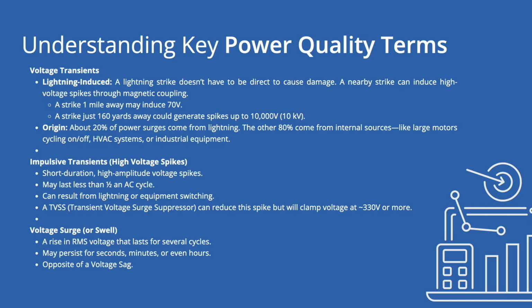Origin. About 20% of power surges come from lightning. The other 80% come from internal sources, like large motors cycling on and off, HVAC systems, or industrial equipment. Impulsive transients, high voltage spikes. Short duration, high amplitude voltage spikes may last less than half an AC cycle, and can result from lightning or equipment switching. A TVSS, transient voltage surge suppressor, can reduce this spike, but will clamp voltage at approximately 330 volts or more.